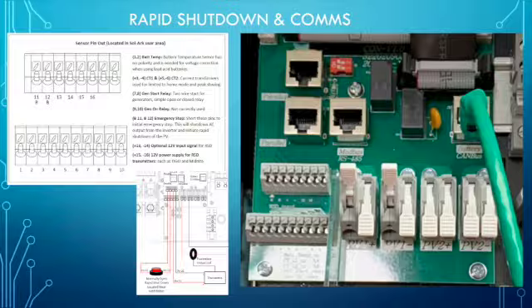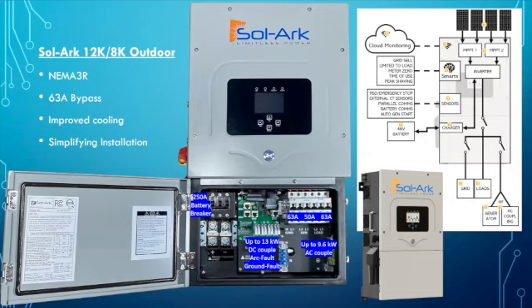Okay, so if we talk about how the bypass works, we have the inverter and we synchronize to the grid, and then we're able to use both the grid and the inverter simultaneously to power the loads. So we can use any amount of power from the grid or the inverter. So it's a seamless bypass.